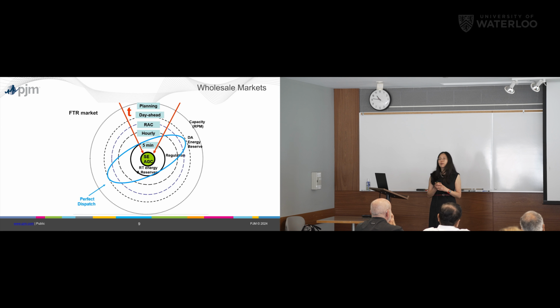Then we have the reliability assessment commitment process. That process bridges the day-ahead financial market with physical power system operation. It evaluates, based on the forecast load for the next operating day, whether there is enough generation to meet the forecast load. If there's not enough, we will call additional slow start units, mainly steam units, could be combined cycle, called before the operating day so they can prepare to come online for the next operating day.